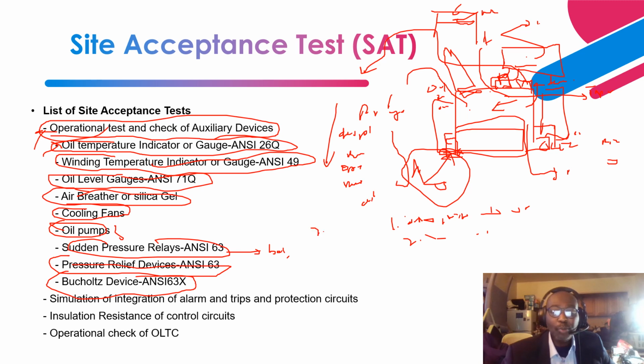Next is to be able to alarm the transformer based on incipient gassing, right? If you have broken connections, broken strands, or tank shorts, that will lead to certain gases being generated, such as acetylene, carbon monoxide, etc. And this gassing, because the gases are lighter, will rise up and accumulate in a chamber in the Buchholz device. Based on the volume of accumulated gas, it is going to activate a mercury switch that will provide an alarm, for action to be taken and investigation to be performed to validate it.